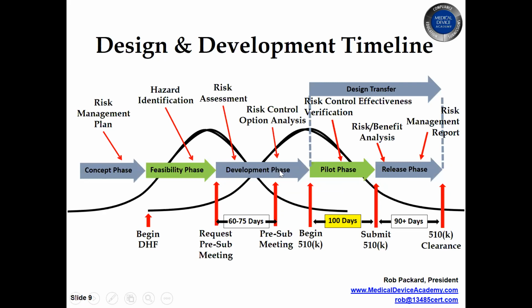So if I have like an 18-month design process, this development phase might be long enough that it makes sense to have two pre-subs in here. But if I have a short development process, then there might only be time for one in here. If I'm making a minor modification to a device, I still might want to do the pre-sub, but I'm going to probably do it at the very beginning of the project, and this feasibility phase might only be weeks. So I might go very quickly from the approval of the project to design inputs, have my pre-sub, and be almost ready to start verification the instant I get the response from the FDA and have that meeting. So that sort of gives you an idea of the timeline that we're talking about here, but it varies a lot based on the project.